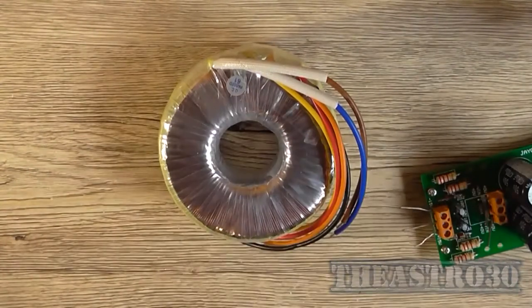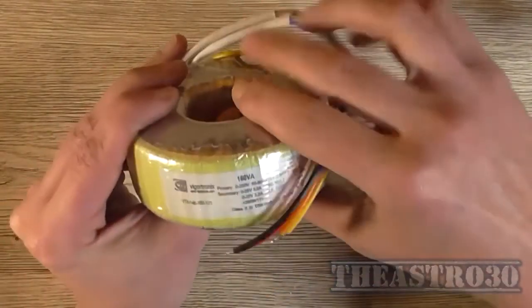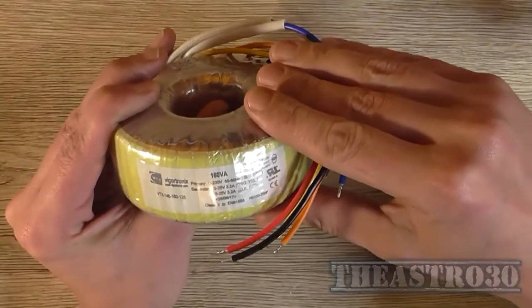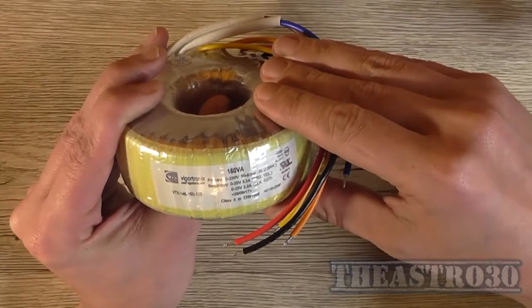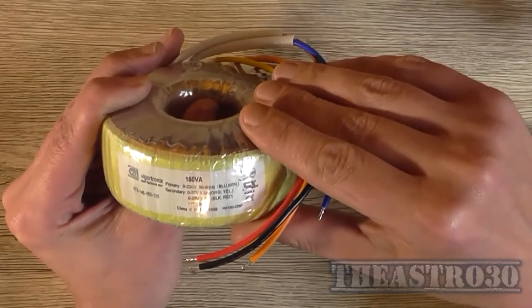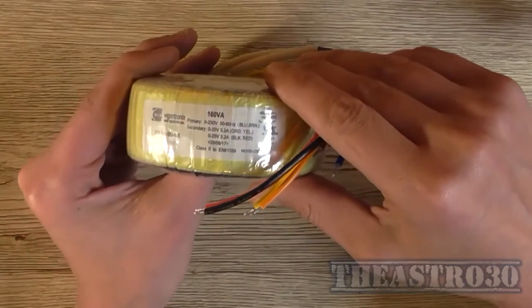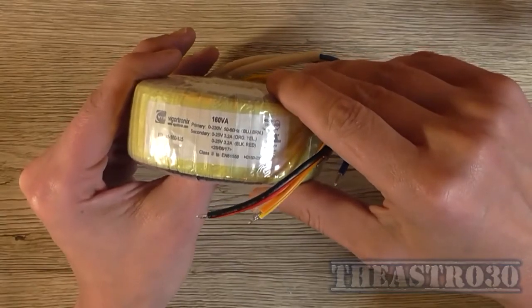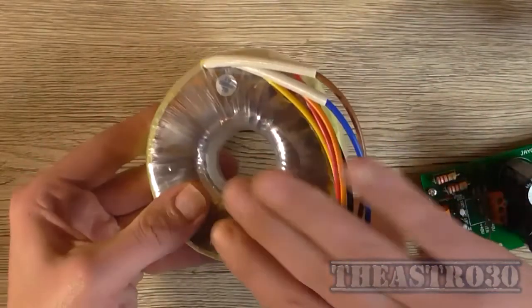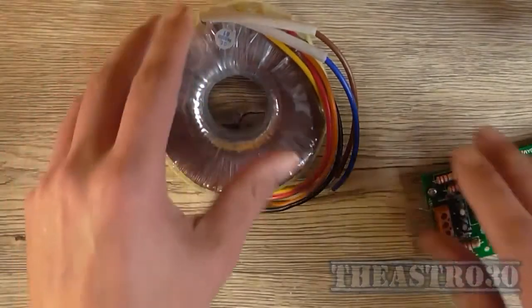There we go. Now, usually they mark on the transformers what fuse to use for the primary, but it doesn't. But I know from experience these 160 VA transformers require a 3 amp line fuse. So that'll be connected - those are the primaries.